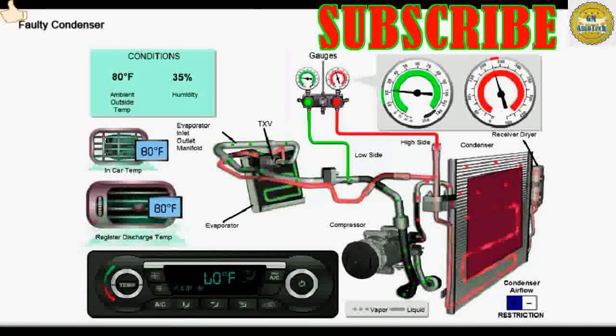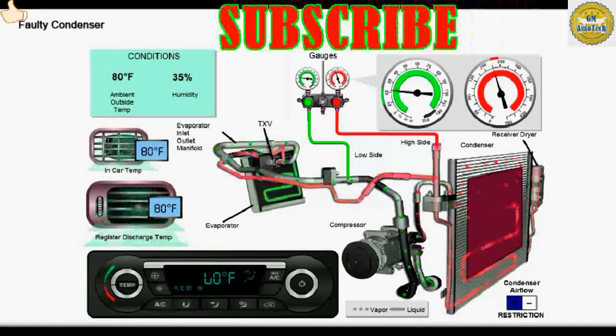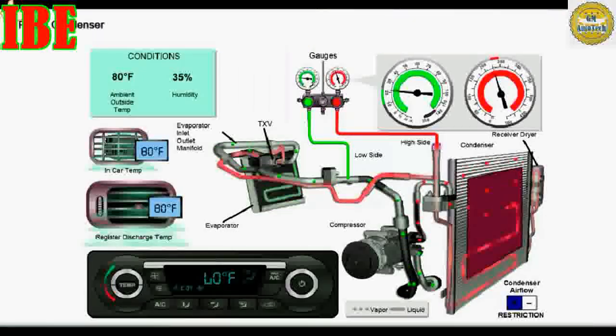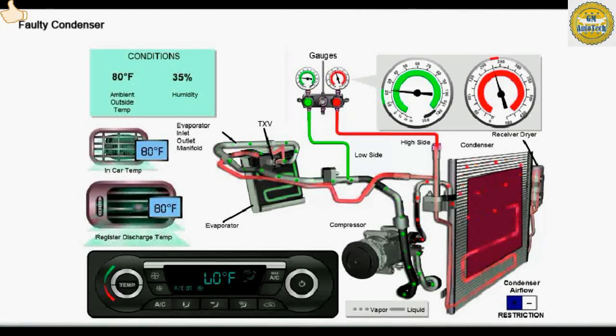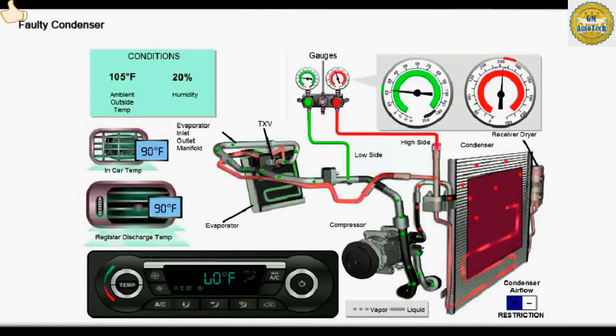When ambient temperature is 27 degrees Celsius (80 degrees Fahrenheit) and relative humidity is between 30 and 60 percent, the high side gauge will read above approximately 225 PSI, and low side pressure will be below approximately 21 PSI.